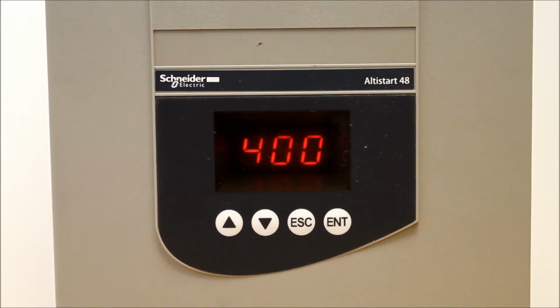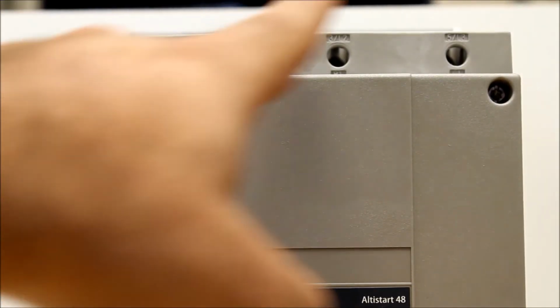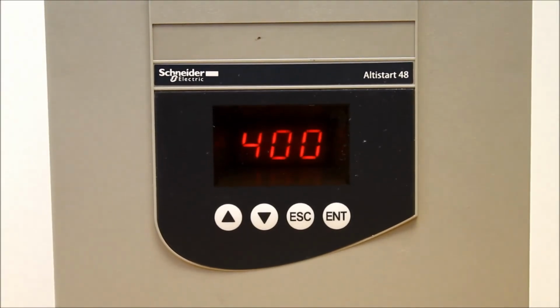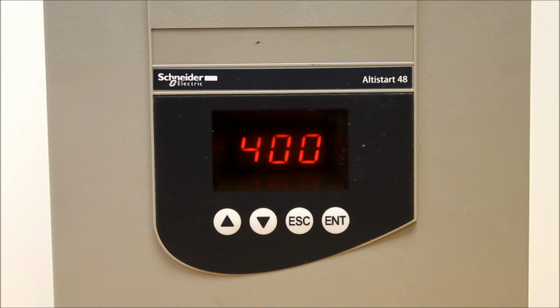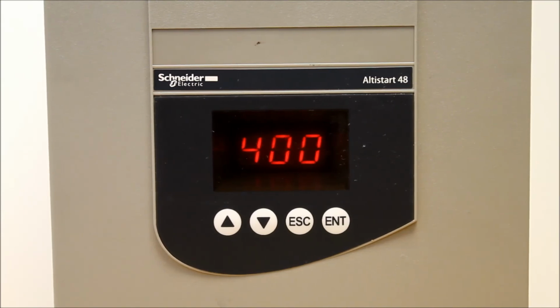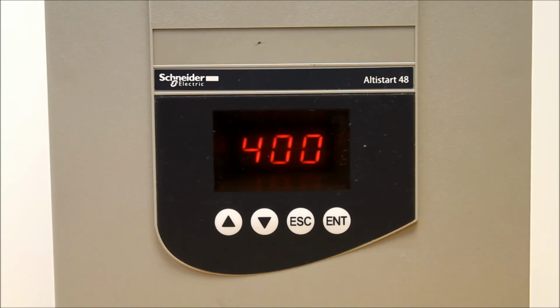So there might be other problems, like a problem with your line power, where you can measure L1, L2, and L3 and make sure those are not dropping too low, because the lower the voltage potential, the higher the current draw. You might have a motor issue. You might have imbalanced current draw by the load. You might want to check the current at each phase coming out of the motor while it's ramping up. Or you may have a motor problem. Maybe the windings are the issue. It might be a very long distance run. The load may be overloaded. The motor may be undersized. There's a number of things that may be going on.